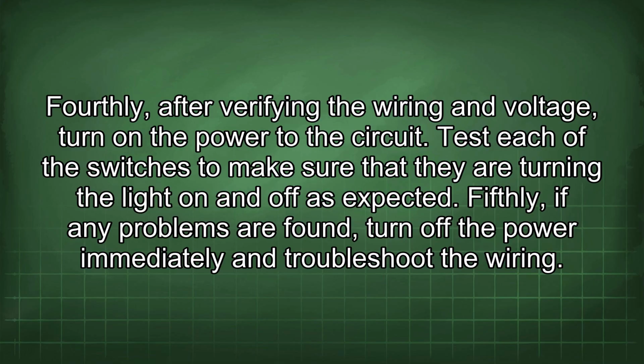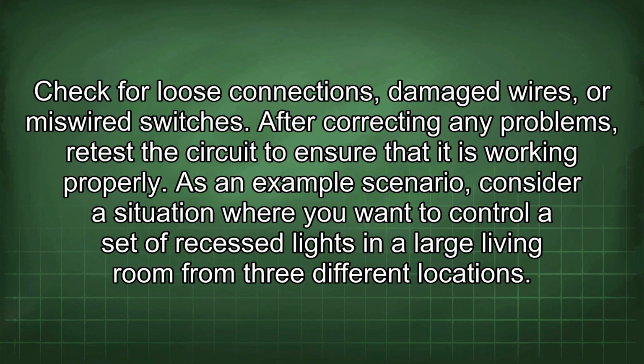Fifthly, if any problems are found, turn off the power immediately and troubleshoot the wiring. Check for loose connections, damaged wires, or miswired switches. After correcting any problems, retest the circuit to ensure that it is working properly. As an example scenario, consider a situation where you want to control a set of recessed lights in a large living room from 3 different locations.